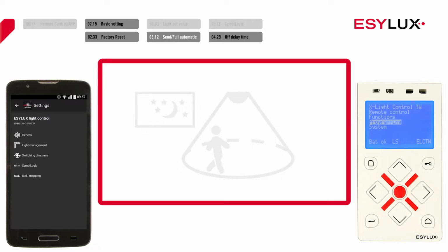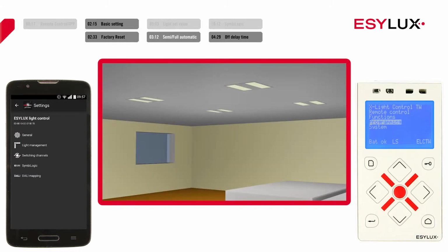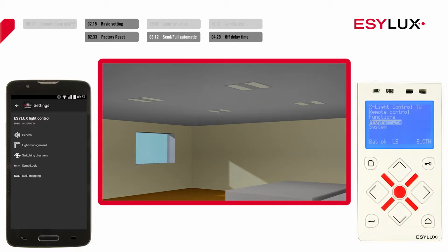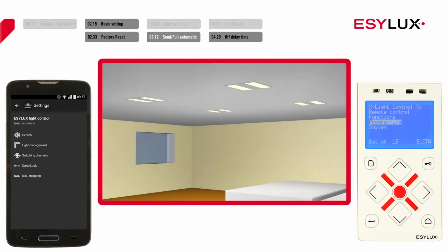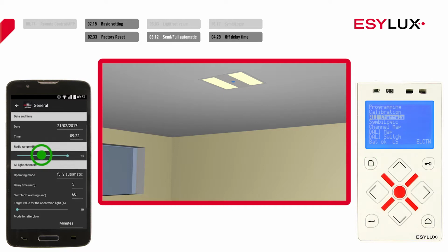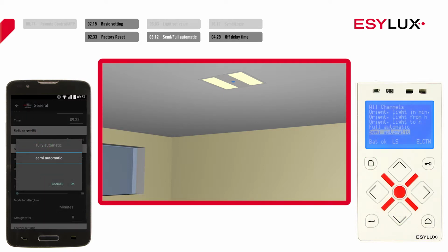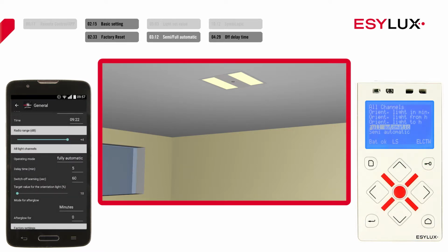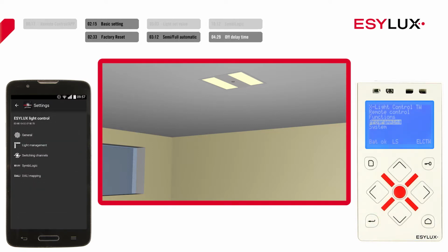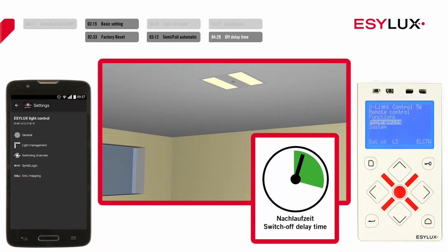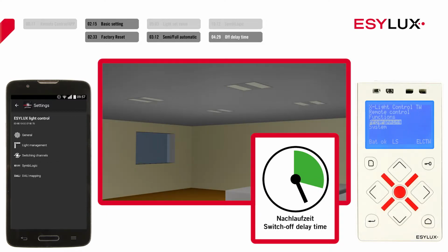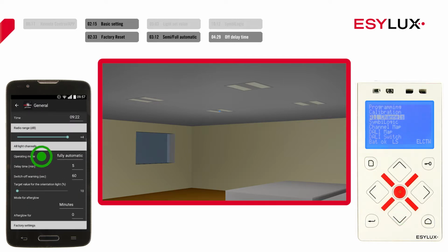Whether you use semi-automatic or fully automatic mode, the light switches off automatically under the following conditions. If the ambient light is brighter than the set target brightness, or if no movement is detected and the switch-off delay time has elapsed. First, set your preferred mode. The switch-off delay time determines how long the light remains switched on after the last detected movement. Select a value between 1 and 240 minutes.